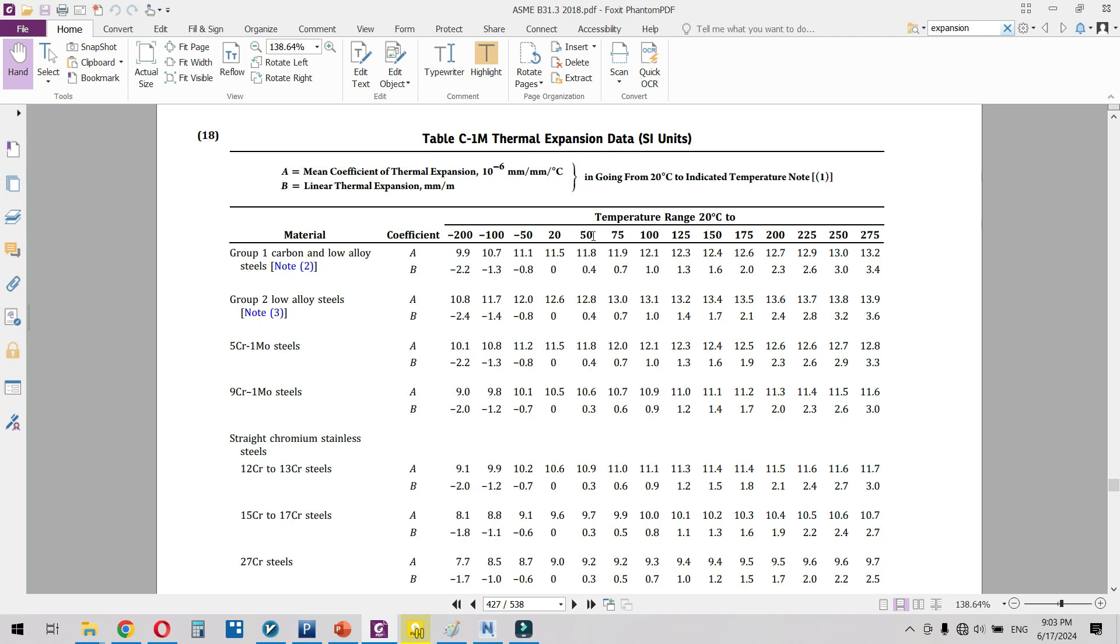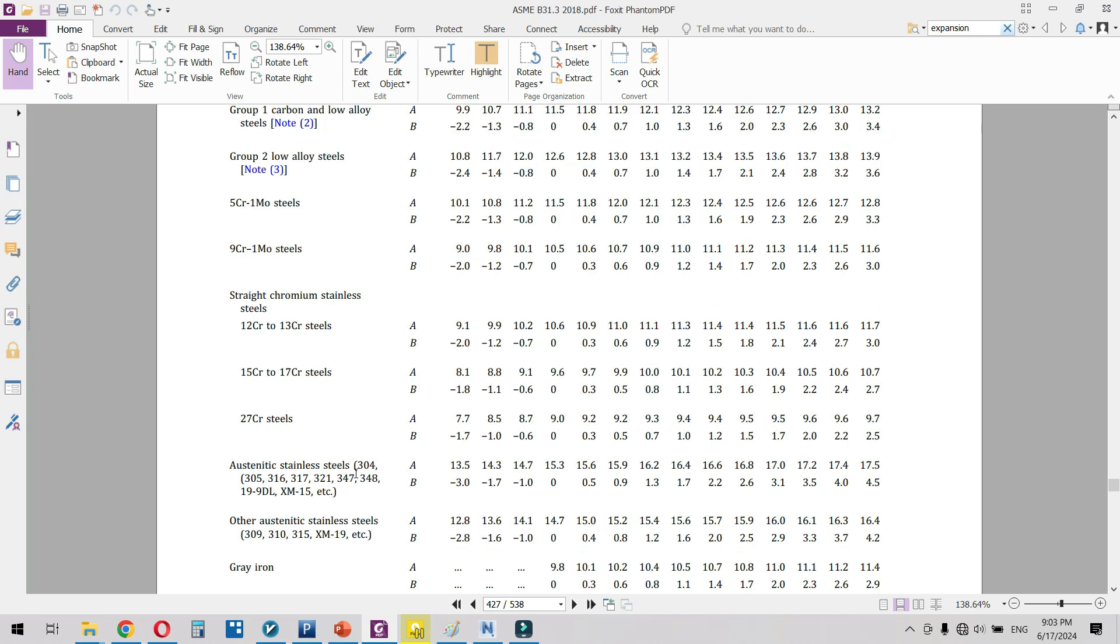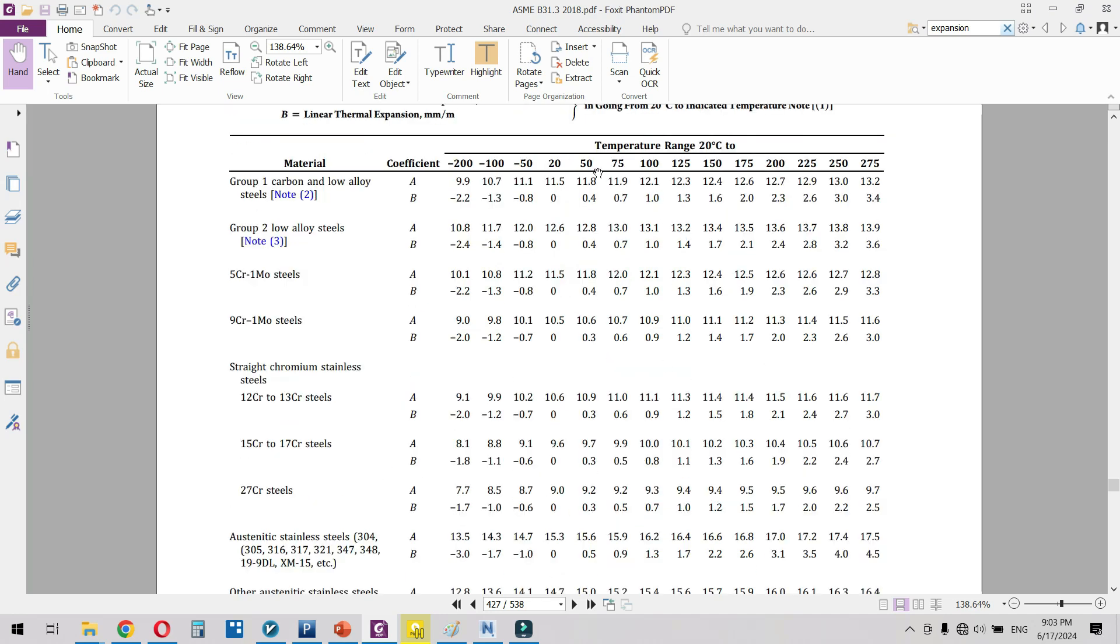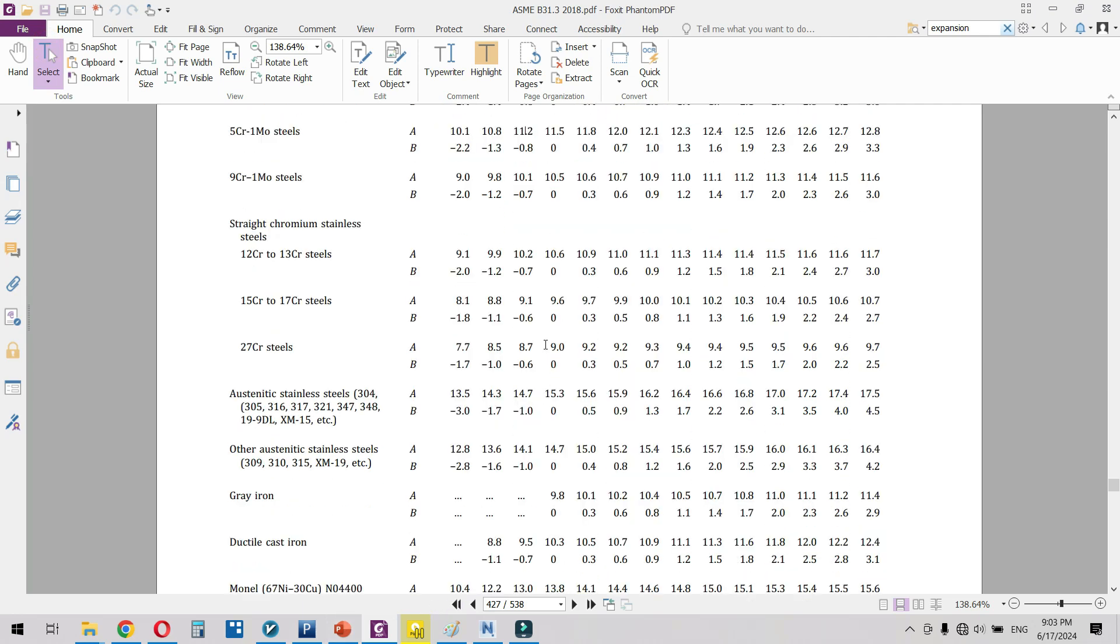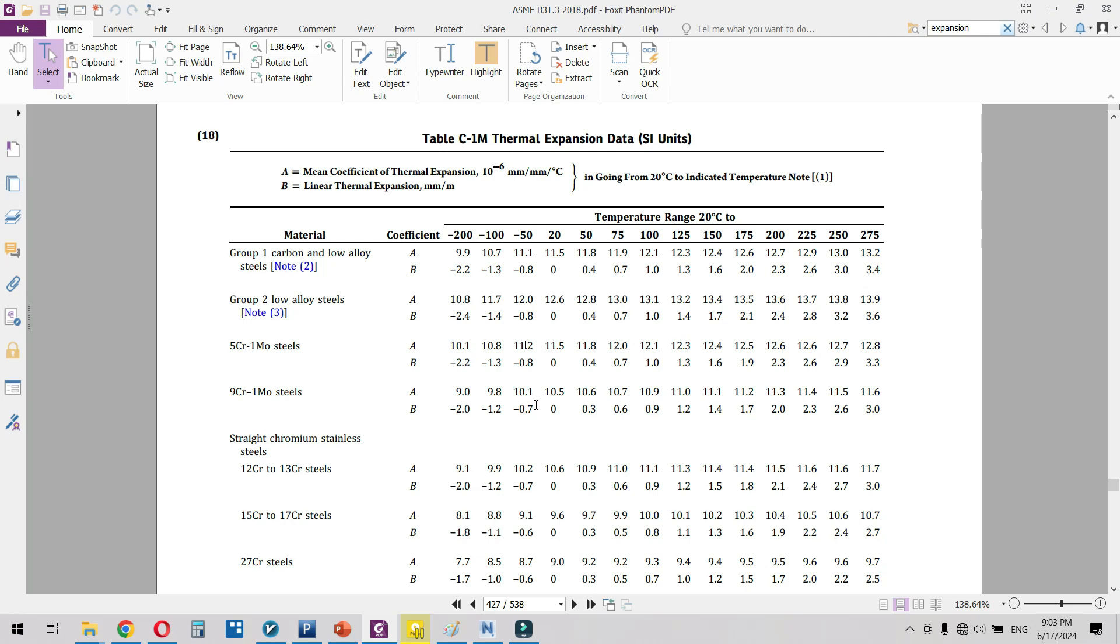For example, consider at 50 degrees Celsius with a type of stainless steels, austenitic stainless steels. At 50 degrees Celsius, as you can see, your piping system if it is from a material of austenitic stainless steel, it will be exposed to much more thermal expansion because the thermal coefficient of austenitic stainless steels is this number, but it is around 12 for carbon steel materials. So you can also use this table for having a background in your mind for comparing your piping system and its flexibility.